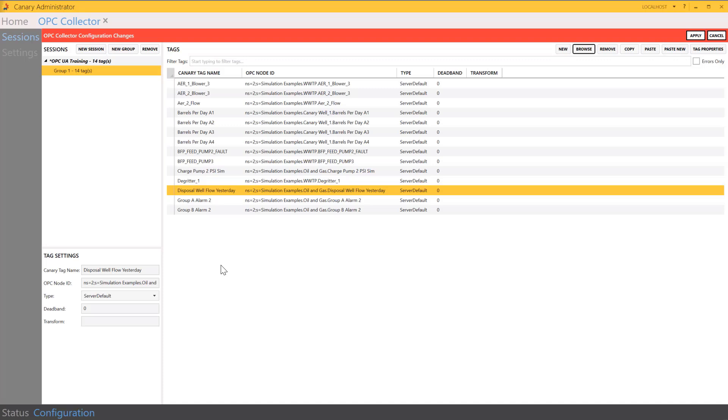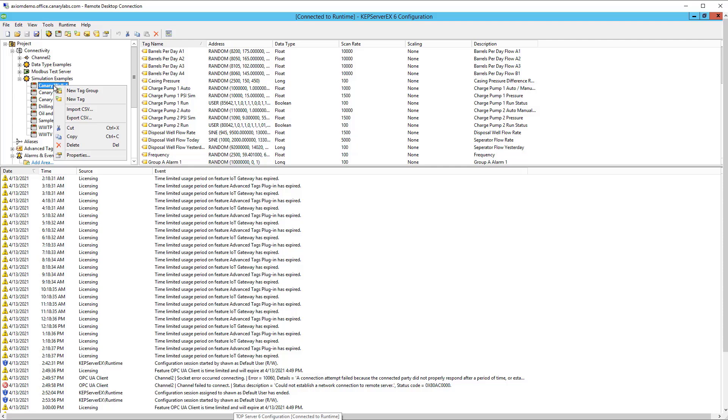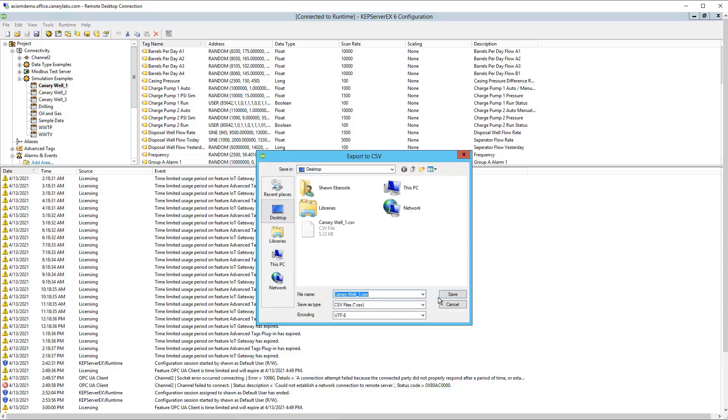And we can achieve that by exporting the tag list from the actual OPC server. So here is the OPC server that I previously connected to from the Canary OPC collector. So I can export the tag list to a CSV file from here by right-clicking on my tag group and choosing to export. And I can save that file.